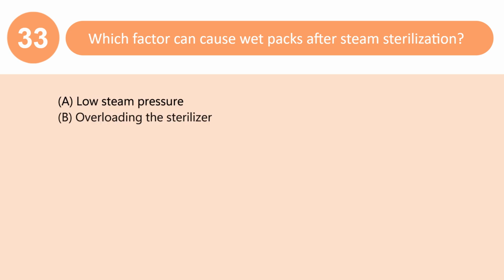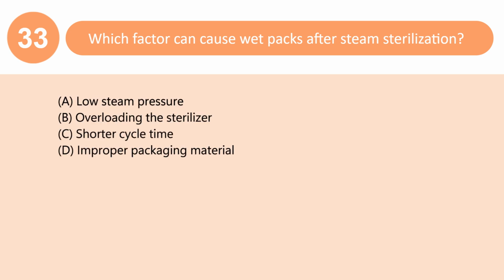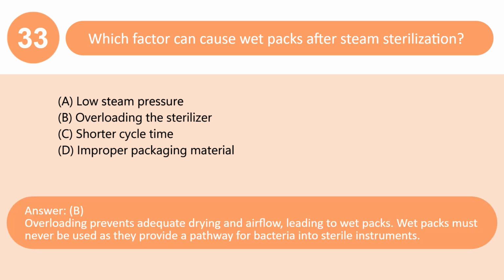Which factor can cause wet packs after steam sterilization? A. Low steam pressure. B. Overloading the sterilizer. C. Shorter cycle time. D. Improper packaging material. Answer: B. Overloading prevents adequate drying and airflow, leading to wet packs. Wet packs must never be used as they provide a pathway for bacteria into sterile instruments.